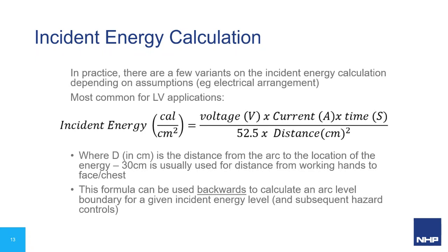And interestingly as well, some people use this formula backwards, which is also an interesting use. So they'll actually calculate the arc flash boundary for a given incident energy level. To put that into practice, to get to a certain distance away from the circuit breaker, you need to have a certain amount of PPE on. So if you're staying away from that main incomer, you can get away with just your regular work outfit. If you're getting closer to that main incomer while it's live, you might have to suit up into something a bit more appropriate. That's something that I've seen examples of, actually painted on the floor of a switch room. So for those more progressive sites, that's something that they can do.